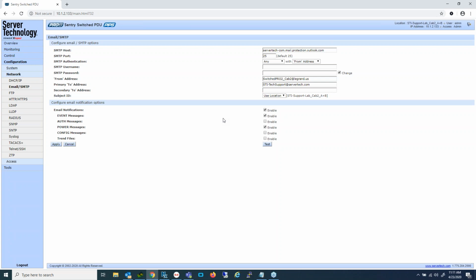For example, if a circuit breaker in your PDU is overloaded and trips, you will get notification. If you have thresholds for temperature and it goes above your high warning or alarm threshold, you will receive a notification. From the power side of things, same examples: if you set thresholds for amperage on a line, phase, or branch, you can receive notifications if those amperage levels are exceeded.